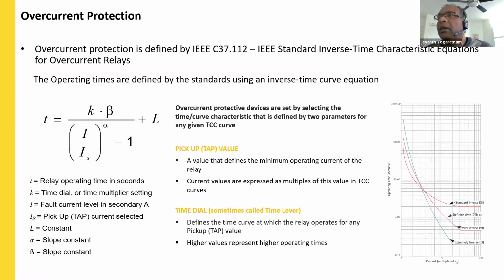So we are all familiar with time overcurrent protection. Technically, it is defined by the IEEE standard C37.112. This is the time inverse curve, and the mathematical model is provided by the standard. By selecting the proper slope constants, alpha and beta, the curves can be categorized, either as a standard inverse curve, definite time curve, or very inverse or extremely inverse. So the curve can be adjusted based on the selection of the constants. However, now the protection relays already have a built-in table, so it helps the user to just select the curve, because the mathematical model has already been embedded in the code.